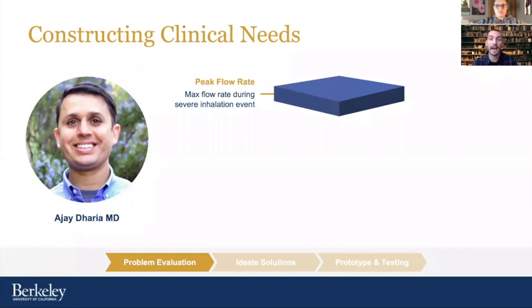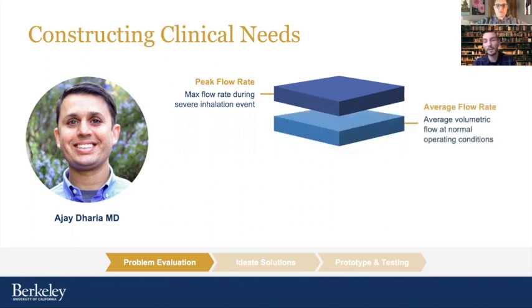The first of which is the peak flow rate. This is if a patient needed to take a high volume of air in at a very short time interval. So this would be something around 1.5 liters per second. The system must also provide an average flow rate during steady operation of about 15 to 20 liters per minute. That's if you're just breathing normally, without exercising or something like that.